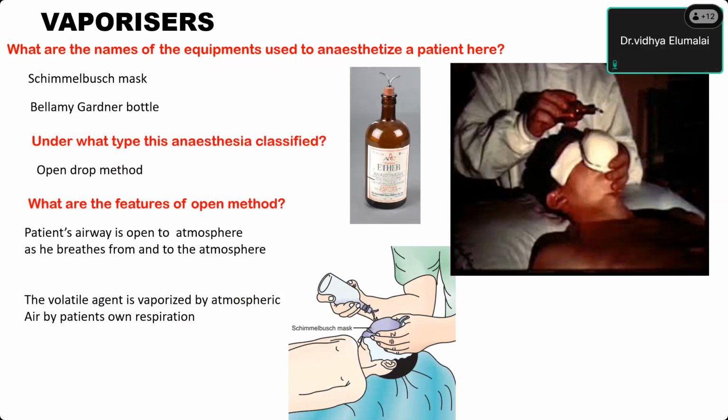Normally, 4 to 6 layers of gauze, because the gauze is interwoven with a gap. It is not a cloth like your dress material. It has a lot of gap in between, the crisscrossing. So it increases the evaporation surface. That is the idea of using this gauze and not the regular dress-like material with a tight woven cloth material. So these 4 to 6 layers of gauze are supposed to increase the surface area for evaporation and produce more amount of vapor.